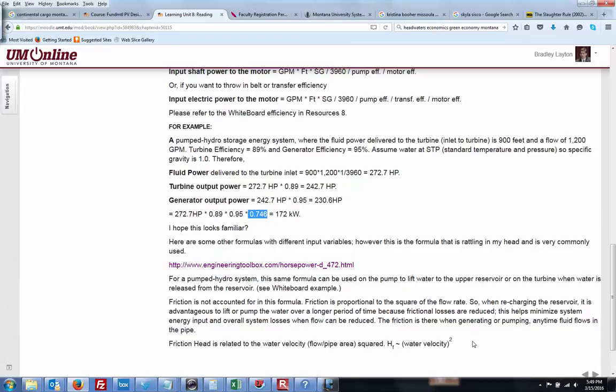Oh, and what he's saying here too, rather than try to jam all the water uphill really quickly, it's going to result in a lot of turbulence losses. It's better to pump it up slowly because the friction head is proportional to water velocity squared. He just says that the friction head, like the pressure that you lose, is proportional to the square of how fast it's pumping. So if you try to pump it twice as fast, you're going to lose 4 times the energy. There's always friction in the pipes. Sure. Yeah.